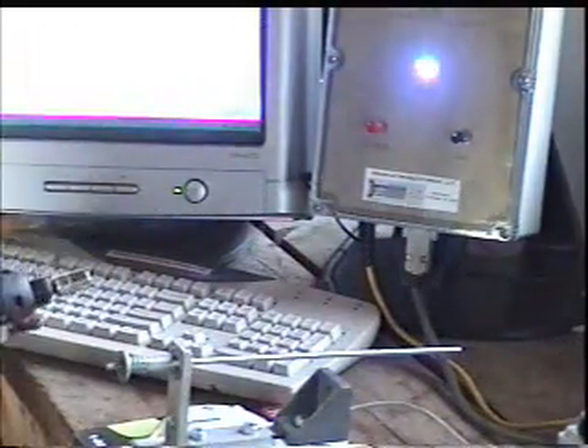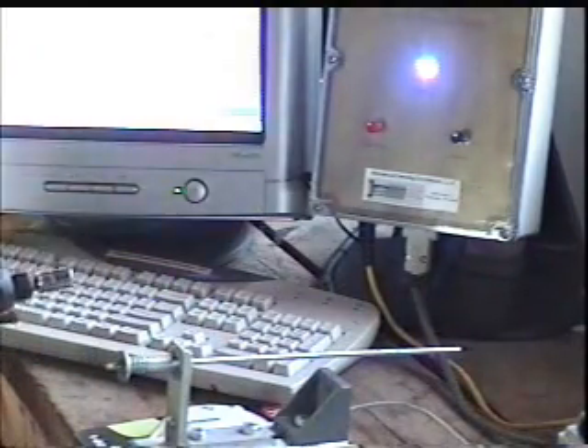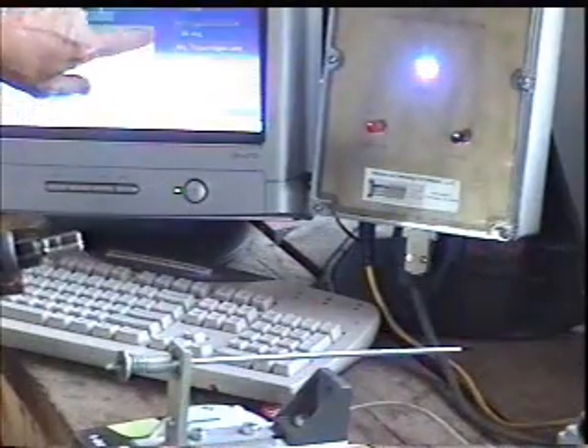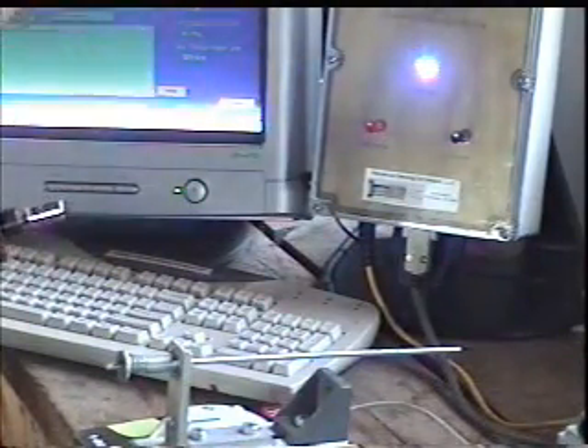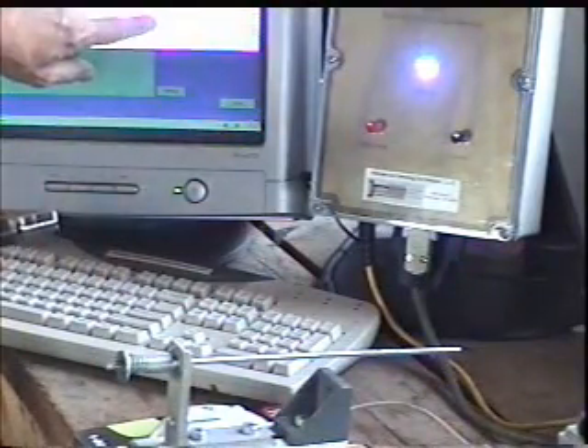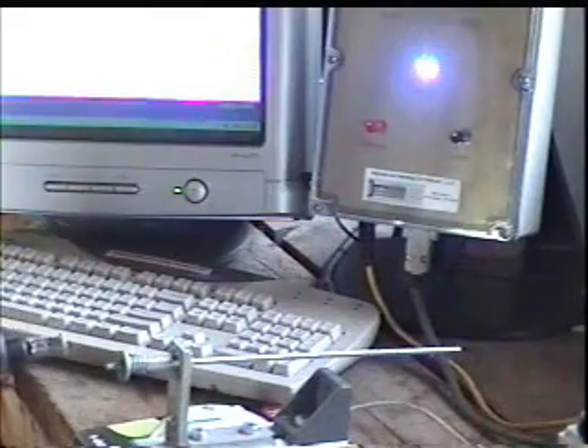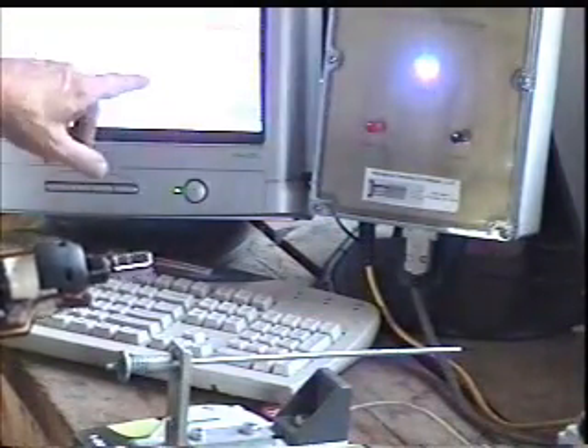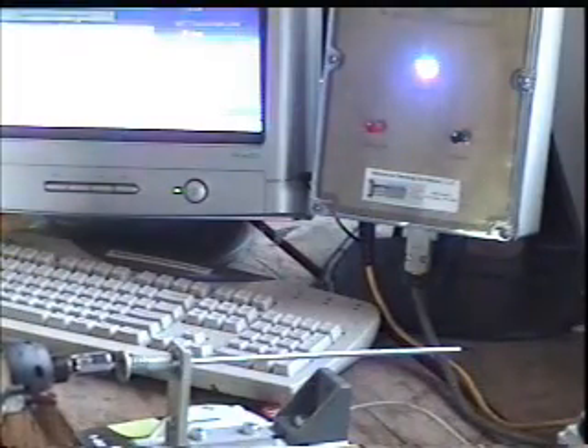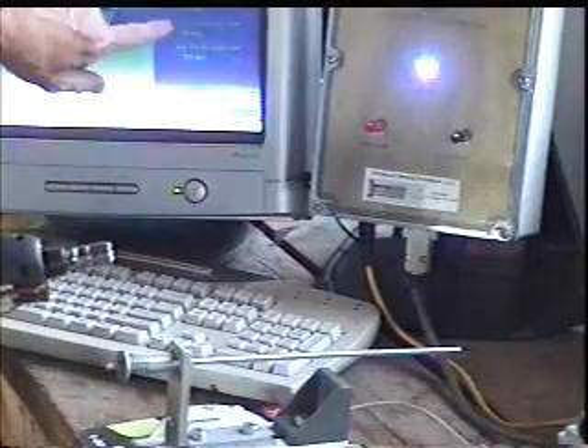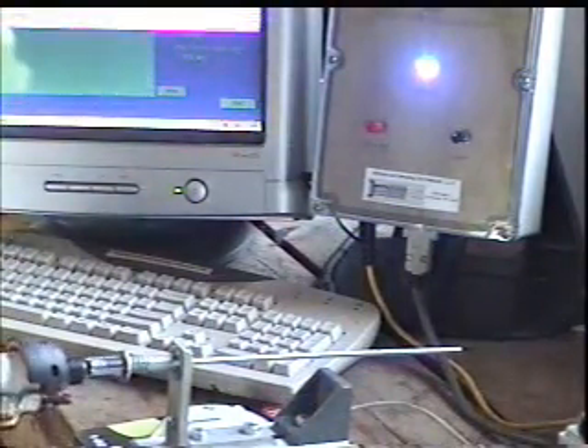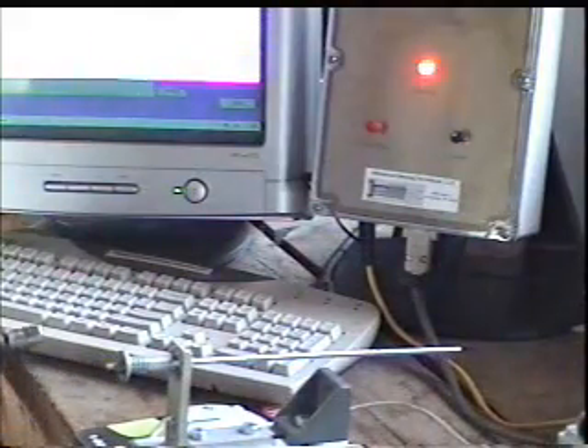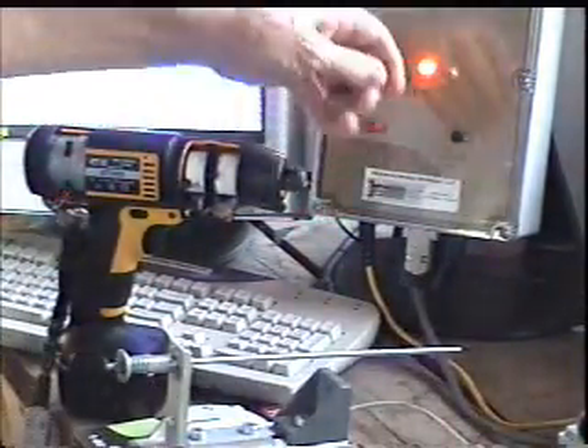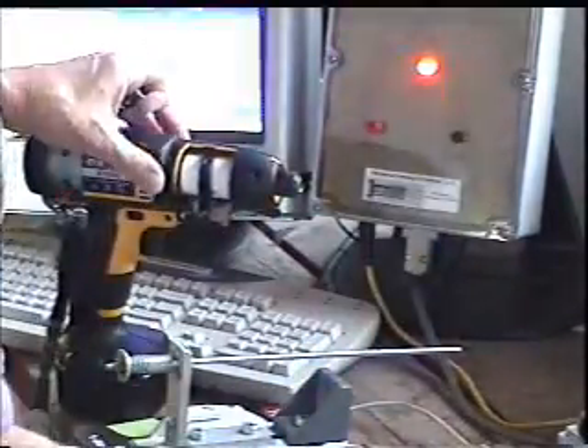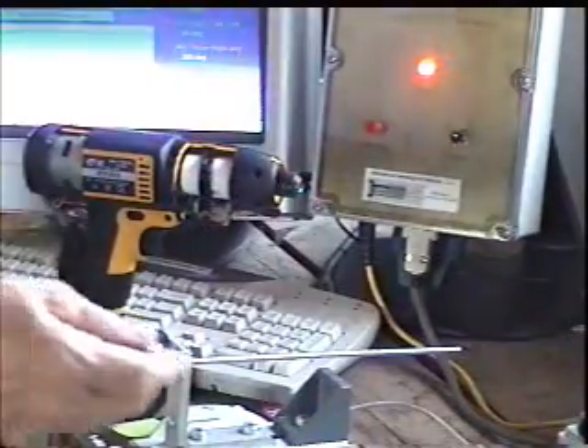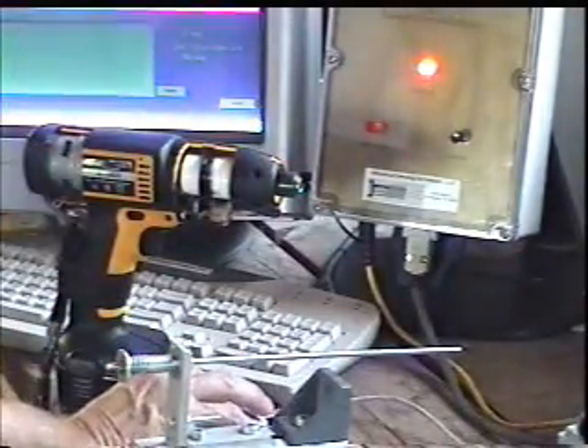It's waiting for a second event, and what should happen is, because torque is increasing, I should fall out of this acceptability window of angle versus torque, where I have 60 degrees as the minimum angle and 360 is the maximum. What should happen is you'll see the red light come on telling me I failed, that I didn't achieve 60 degrees before I got to the 1 Newton meter threshold. And there we failed. And the reason that we failed is minimum angle was not met. Okay, now I can go back to the computer and say, we'll do that again.